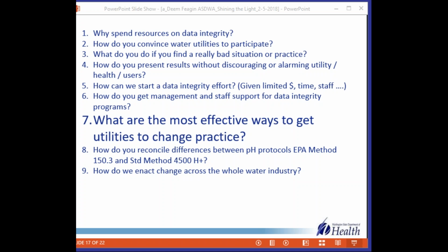And so you can do it right then and it's done. Another thing we've done on the turbidity settings is to send a letter and a form to each system and ask them to record their settings from their turbidimeters. We give them what we think are the optimal settings, and we ask them to verify that they have set up their turbidimeters the way we think they should. This also brings some back and forth. If they don't agree with the setting, they give us a call. We have a chance to talk to them about it. So that's been pretty effective too.